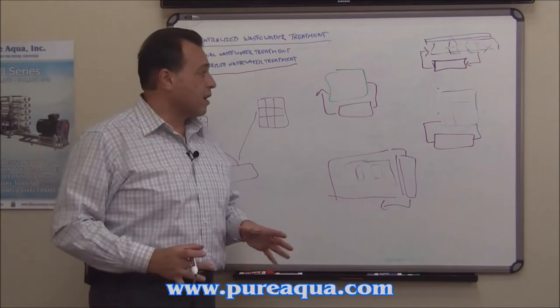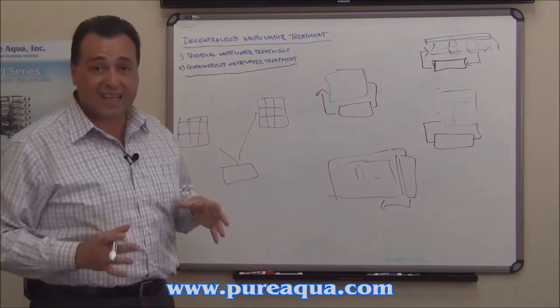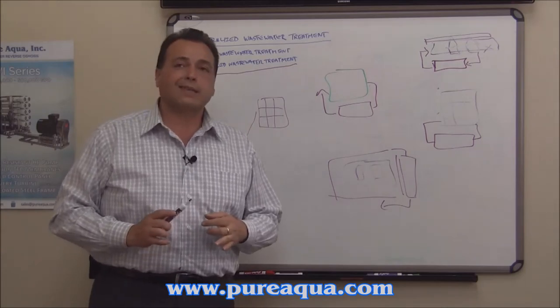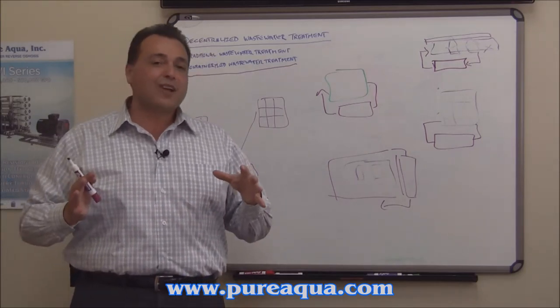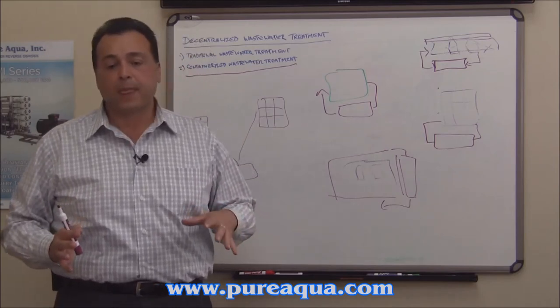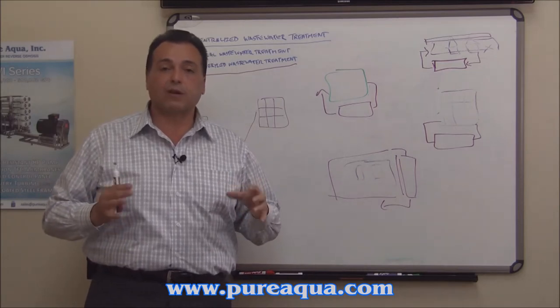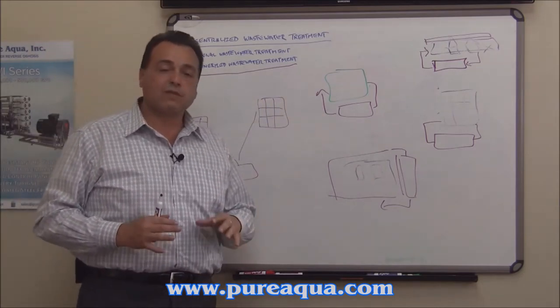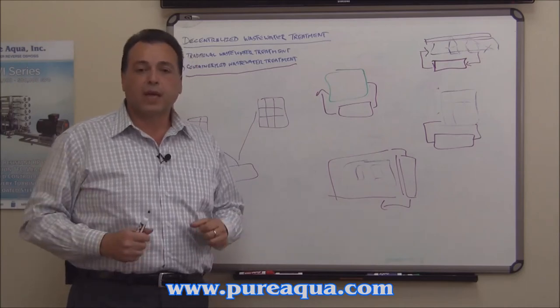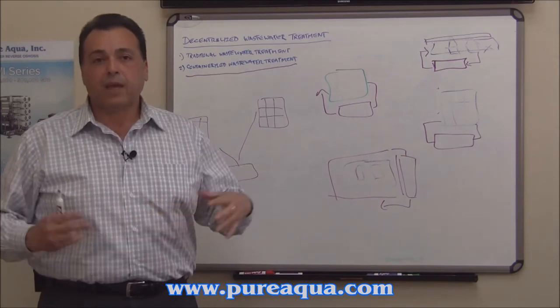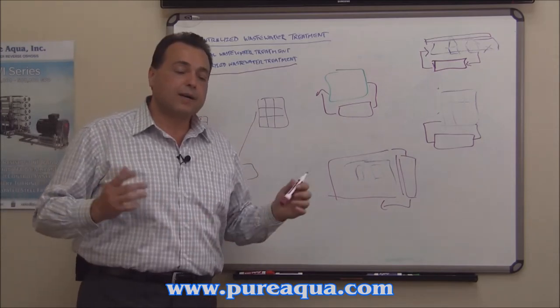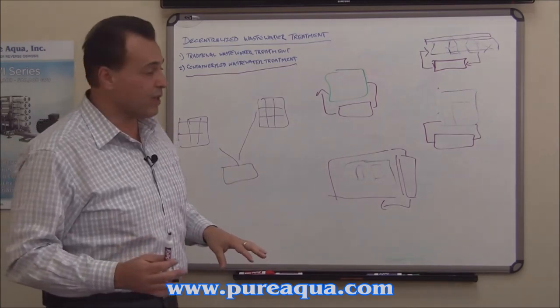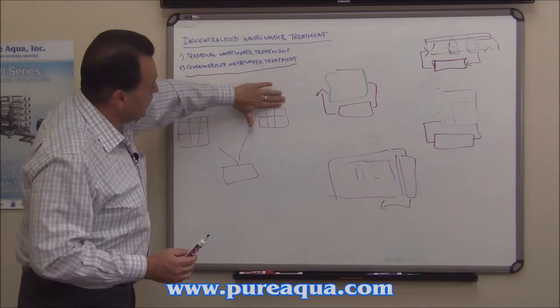The benefits of a containerized wastewater treatment system include ease of deployment — though it's certainly not plug-and-play. It requires some site preparation: in some cases an accumulation tank or equalization tank for the inlet. But generally the preparation is very minimal — it ranges from having a crane on site, a cement slab, proper piping, and an electrician to connect the system. These systems come in 20-foot or 40-foot containers.